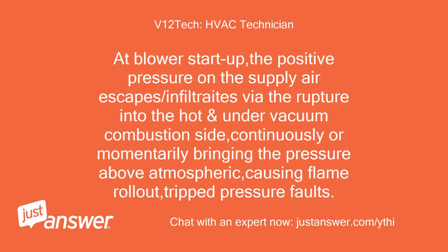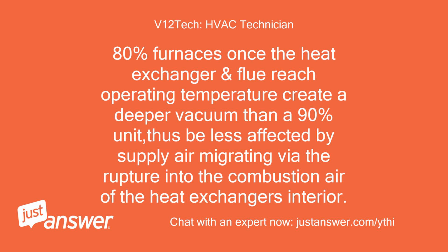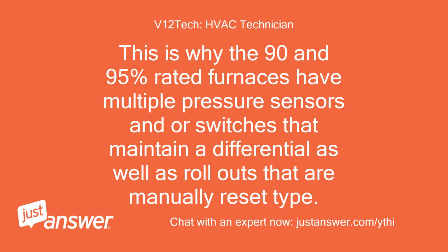At blower startup, the positive pressure on the supply air escapes/infiltrates via the rupture into the hot, under-vacuum combustion side, continuously or momentarily bringing the pressure above atmospheric, causing flame rollout and tripped pressure faults. 80% furnaces, once the heat exchanger and flue reach operating temperature, create a deeper vacuum than a 90% unit, thus being less affected by supply air migrating via the rupture into the combustion air of the heat exchanger's interior. This is why the 90 and 95% rated furnaces have multiple pressure sensors and/or switches that maintain a differential, as well as rollouts that are manual reset type.